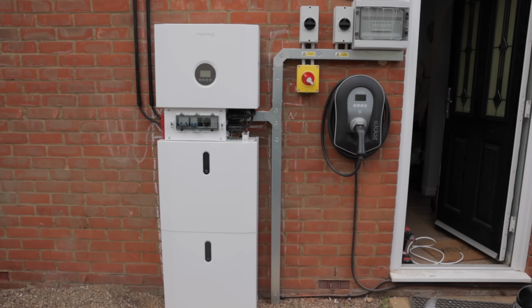But the ideal, and this is one of the main points of this video, the ideal is to get the system designed properly to start with, which means you need to know what level of loads you have running in your house at any given time. What is your maximum demand? What's the worst case scenario? Maybe when you've got the hot tub running and the sauna going and the oven and the toaster and the air fryer. Maybe it's not very often, but ideally you want to size the system so that it can cope with your maximum demand.